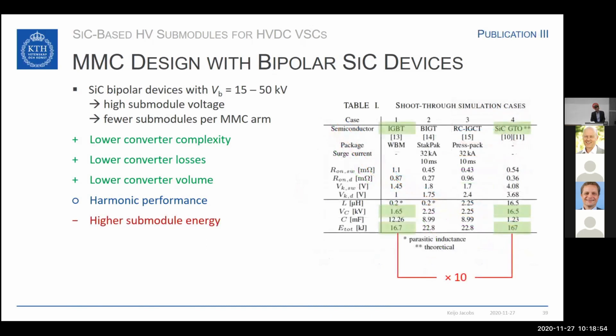A big issue with such a design is the higher submodule energy. And for this, in publication 3, we have compared different design cases. Here I have marked the standard solution with an IGBT with a nominal voltage of 1.65 kV. And you can see that the energy is 16.7 kilojoule, which is already quite a lot. However, for the proposed design, you would get an energy that is 10 times higher, which is critical.